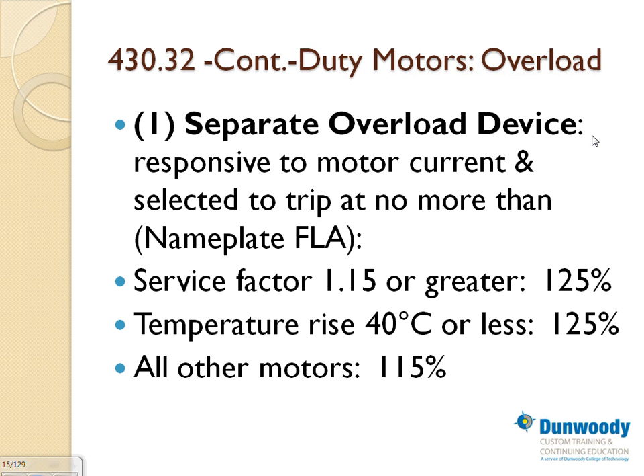Everybody knows for motors, because they're very expensive, guys: air handling units, chillers, rooftop units, CRAC units. You maintain data centers here, so you have computer cooling units. These are very expensive pieces of equipment, so you're not going to depend on a fuse or a circuit breaker to protect this equipment. We hope not. So what they do is they have multiple protection.